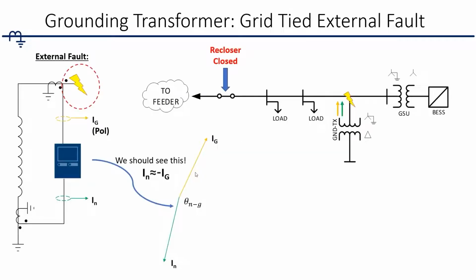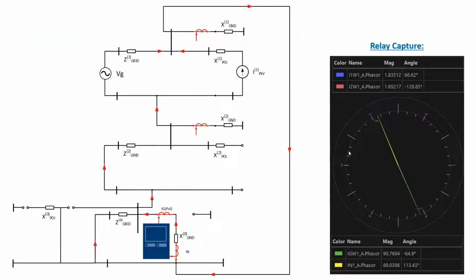So let's move the fault. We said, okay, that's an internal fault. Let's slide it out on the network somewhere. So now it's outside of the zone of protection. For this we would expect the relay to restrain and not operate. We would expect to see, like we said, 180 degrees, so a pretty wide angle between the ground and neutral measurements. As we slide it along somewhere in this network, even out onto the utility system, we would expect to see the same thing. This was kind of close in to the transformer from what I remember. It wasn't too far away, and it is grid tied at the time.